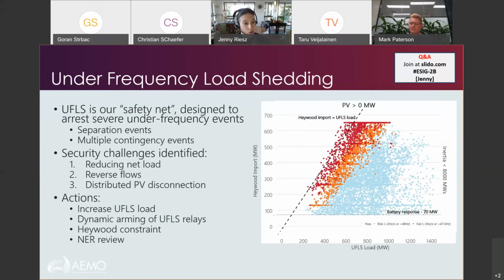There's a series of issues we've identified with under-frequency load shedding being impacted by distributed PV. It reduces the net load on those circuits, so we've got less load to trip to arrest the frequency decline. And we eventually see circuits go into reverse flows, which means when you trip that circuit, you're tripping a generator rather than a load, and it actually exacerbates the frequency decline rather than helping to correct it. And finally, the distributed PV itself actually fights against the UFLS scheme because it's tripping off as the frequency drops. And so it's making the challenge even harder.